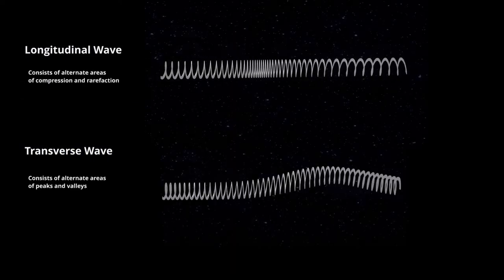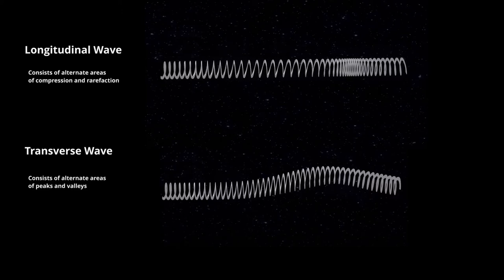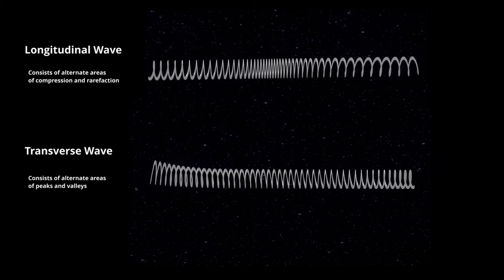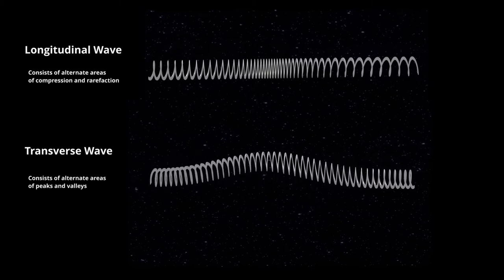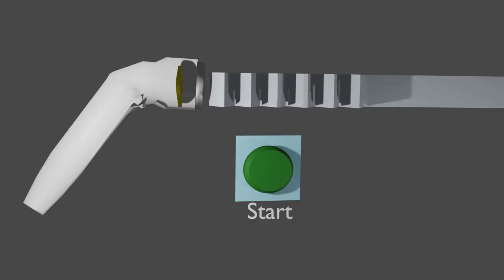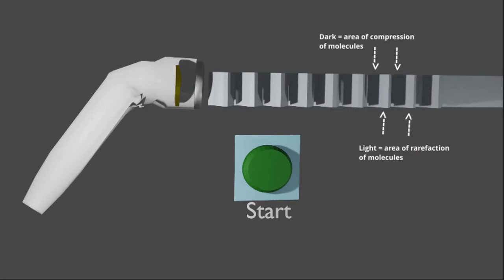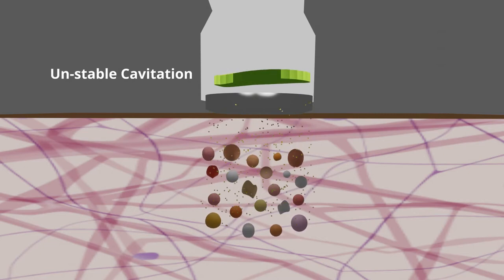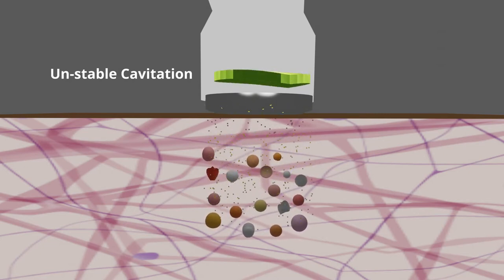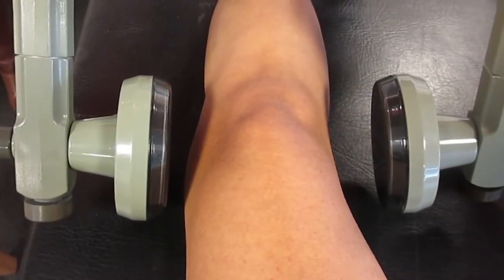There are two types of SWD units which create heat in different ways. Inductive SWD units contain coils which create a magnetic field. This field projects forward into the body and generates a circular electric field within the target tissue. Typically, the coils are confined to flexible cables or within a rigid drum. Capacitive SWD units use condenser plates to transfer oscillations of electric fields between the plates. The target tissue is placed between the condenser plates and acts as a capacitor to store electrical charge, resulting in local heating of the tissue.